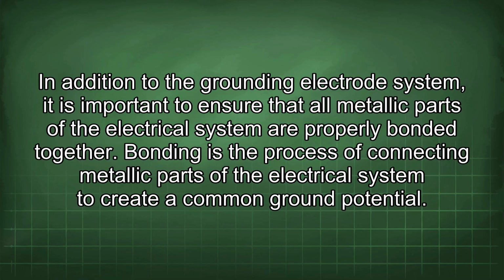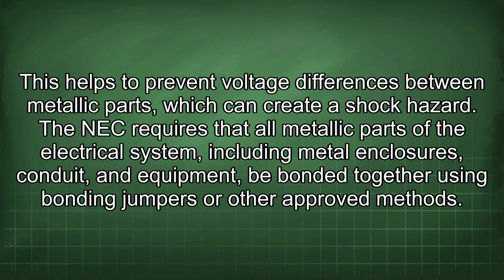In addition to the grounding electrode system, it is important to ensure that all metallic parts of the electrical system are properly bonded together. Bonding is the process of connecting metallic parts of the electrical system to create a common ground potential. This helps to prevent voltage differences between metallic parts, which can create a shock hazard. The NEC requires that all metallic parts of the electrical system, including metal enclosures, conduit, and equipment, be bonded together using bonding jumpers or other approved methods.